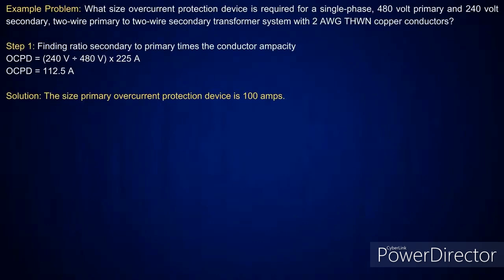Now, this one is a two-wire primary, two-wire secondary, and we looked at that a while ago. So we've got a 480 volt primary and a 240 volt secondary. How am I going to determine the size of that primary overcurrent protection device upstream? Well, all I'm going to do is find the ratio of the primary times the conductor ampacity. So I'm going to divide the 480 volts into the 240 volts, and I've got 225 amps. That 225 amps is going to give me 112.5 amps, and then I'm able to drop down on the primary, and that overcurrent protection device would be required to be 100 amps.